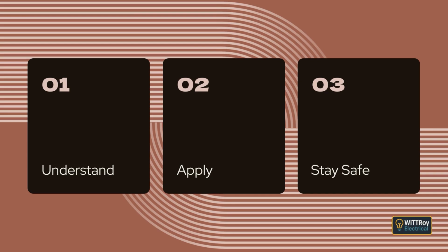Under National Building Code requirements, bulk thermal insulation is prevalent in modern building construction within roofs, ceilings, walls, and floors depending on the building and its climate zone. Bulk insulation may also be retrofitted, added, or altered, and precautions will need to be applied by the insulation installer where recessed downlights are present. In Australia, AS 3999 and in New Zealand, AS/NZS 4246 include instructions for insulation installers in relation to clearances from recessed downlights. The presence of bulk insulation, particularly over the rear of ceiling-mounted downlights, can impair cooling air circulation. Unless the manufacturer specifies otherwise, the space above the luminaire shall remain clear and a warning sign installed.